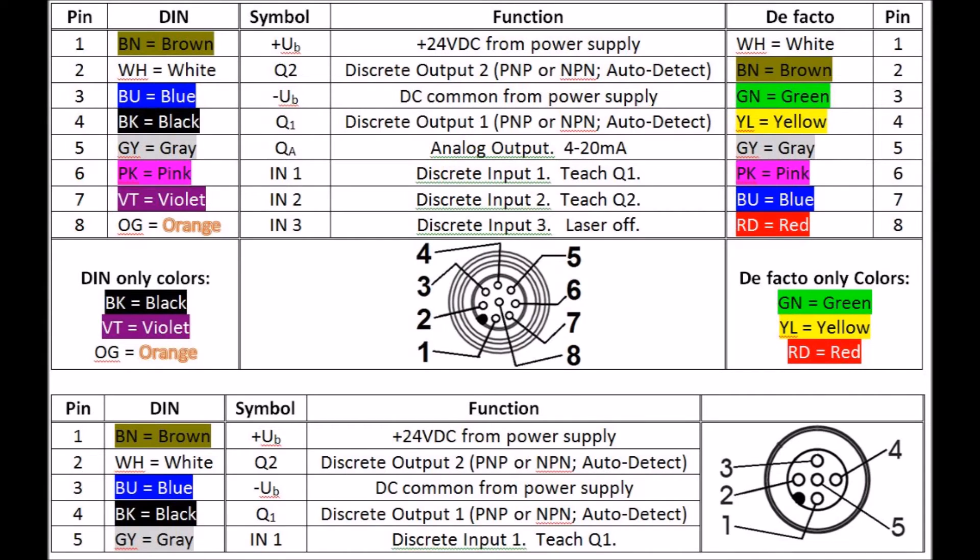Starting with this sensor, we're going to be using the new DIN color code standard for 8-pin M12 connectors. You can see that here on the left of this table, and on the right is a cross-reference to the old de facto standard that we have on all of our existing cables. There's a link to this table in the comments below.